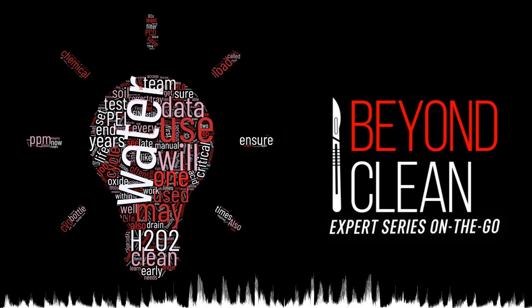When a hydrogen peroxide solution is vaporized, its molecules are freed from one another to travel the world in gaseous form. In an SPD, this world they travel is the chamber of a low-temperature sterilizer and the medical devices it contains. This gaseous state allows the reactive H2O2 molecules to reach deep into these medical devices and find bugs hidden in lumens, cracks, and crevices.